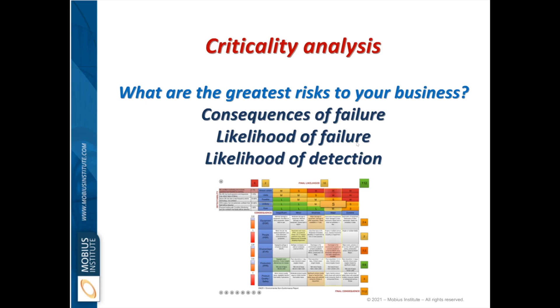Take an electric motor: the rotor bars could crack and fail, the bearings might fail, the rotor may be out of balance, or the rotor might rub against the stator. There are lots of different ways it can fail, and the consequences of failure and the likelihood of detection could be quite different. The likelihood of failing because of a bearing fault has a certain probability of occurring, while the probability of the rotor rubbing against the stator might be far less likely.